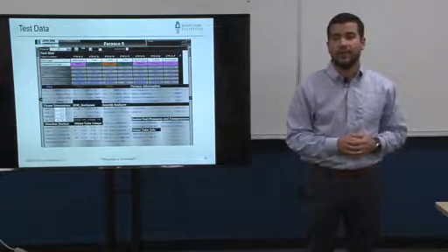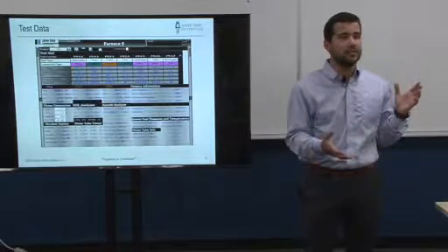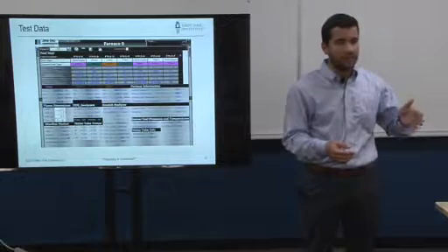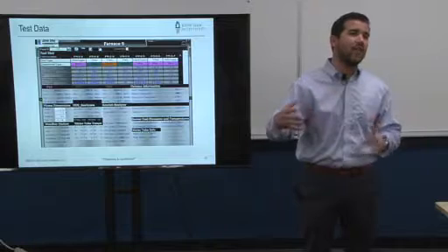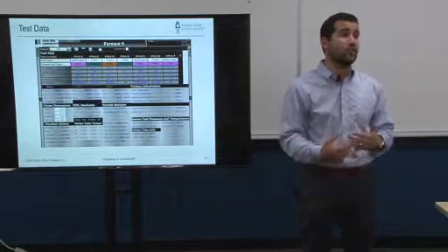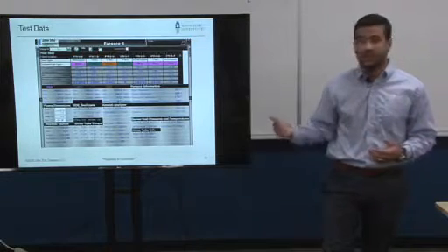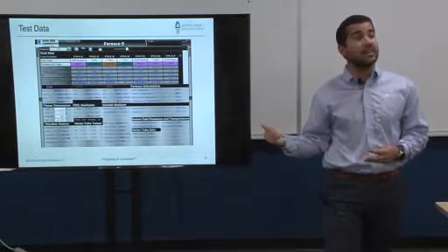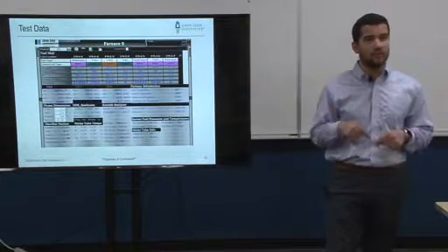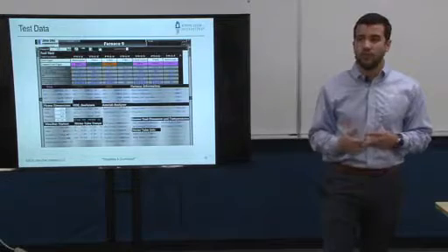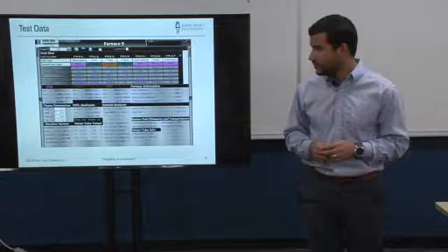As you know, I think Mark talked about it, there's a capacity curve, where you have on the y-axis your heat release, and on the x-axis your pressure. One of the things in order to create that curve for your customer is you need to understand the coefficient of discharge, which I think you guys talked about too. And this is the way for us to get that coefficient of discharge, by understanding what the pressure is here in Tulsa, with the temperature and the fuel composition. So pretty cool. That's a really nice observation.